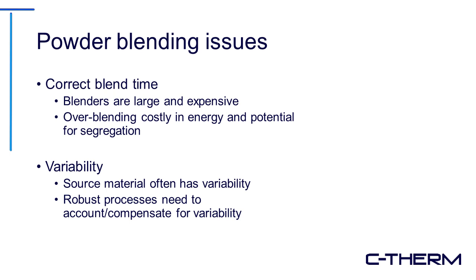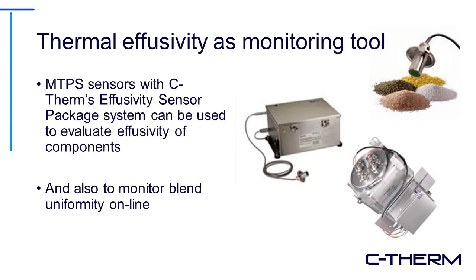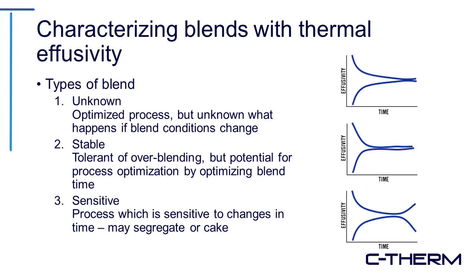So if you understand the blend well enough, you can design a process that will compensate for starting material variability, so that even if your starting material is variable, you get a consistent end product coming out the other side. And that's where we get into using thermal effusivity as a process monitoring tool. This system here is called the Effusivity Sensor Package System, and it's a process analytical technology system using the same technology as the Modified Transient Plane Source sensor my colleague Jordan was speaking to earlier. You can use this package to monitor blend uniformity online, at line, or even inline with the process, depending on the needs of the group.